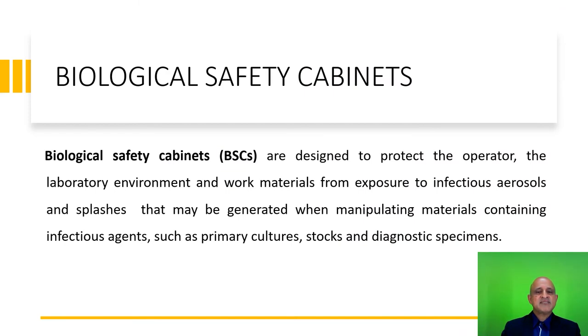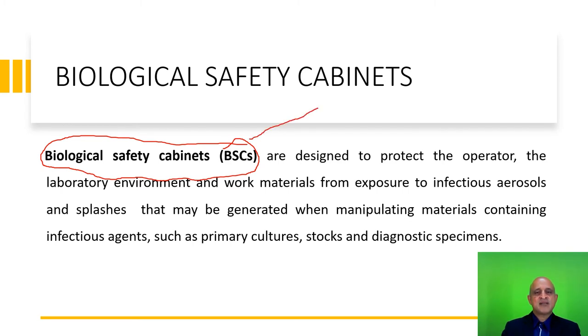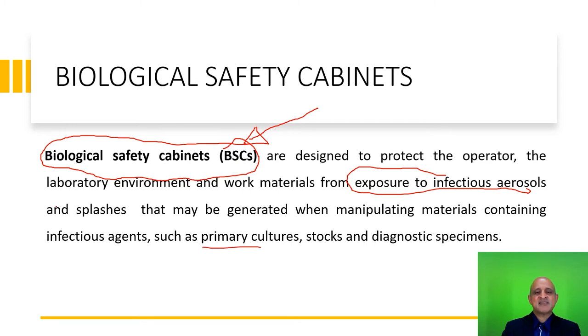Part 3 of the manual covers basic laboratory equipment, focusing on the biological safety cabinet. If you are working in a laboratory with basic facilities, a biological safety cabinet will greatly enhance the degree of control you have over the escape of the biological agent. The biological safety cabinet essentially serves as a workspace which prevents exposure to infectious aerosols and splashes that may be generated when handling materials containing infectious agents such as primary cultures, stocks, and diagnostic specimens.